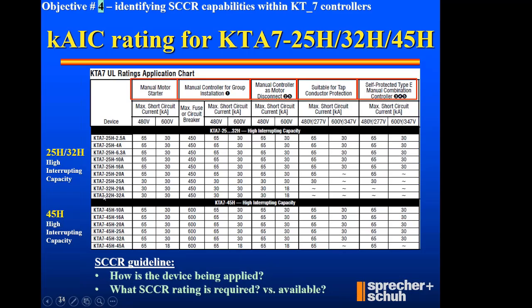Get into the higher amps. Now a 29, I can't get a rating on a 29 or 32. Oh, I go to the bigger product. 45H is bigger in size. Well, I can get 65 KAIC at any of those ranges now. So that gives you an idea that the KAIC approval is for the component only, for the KT7 device, located right after the selection page.